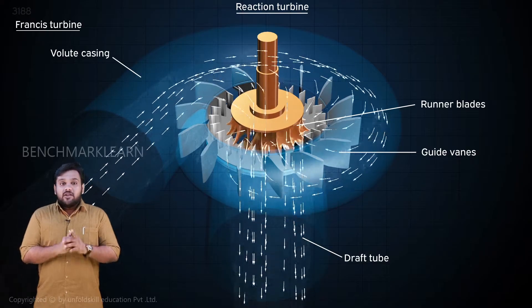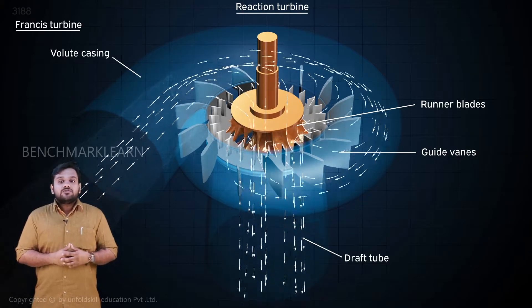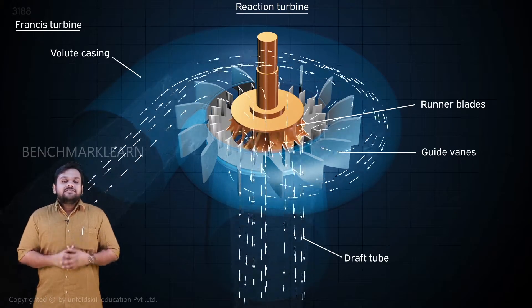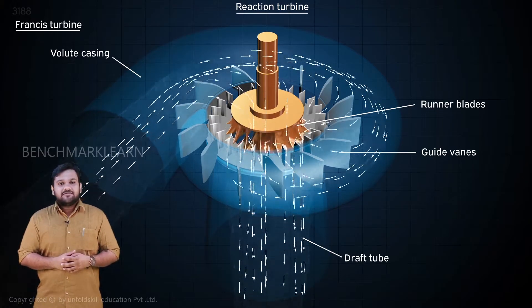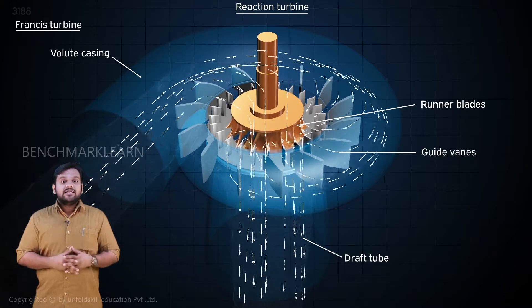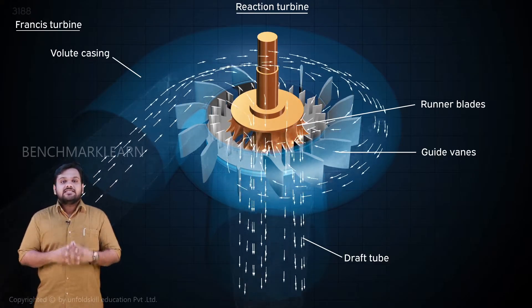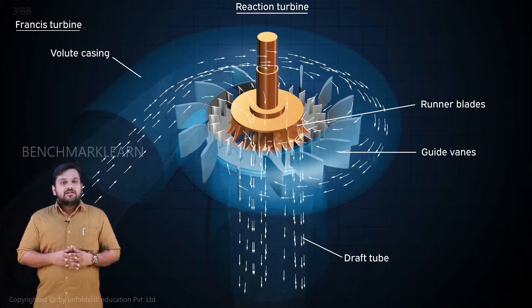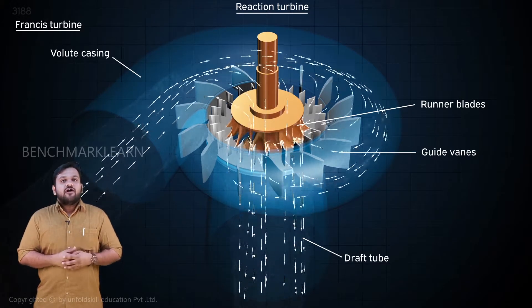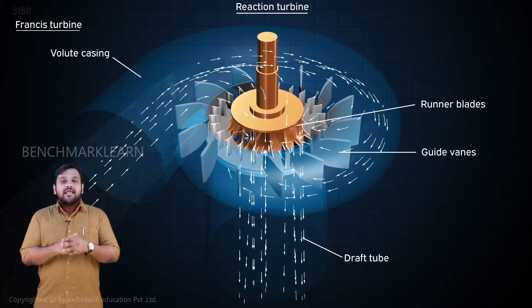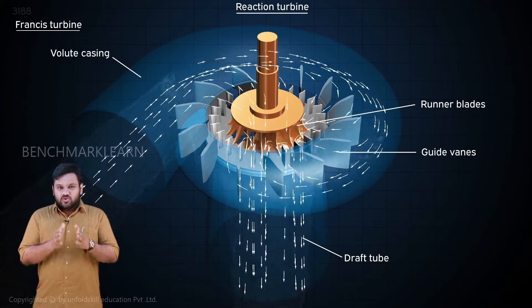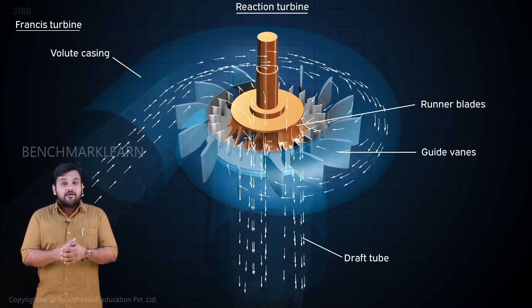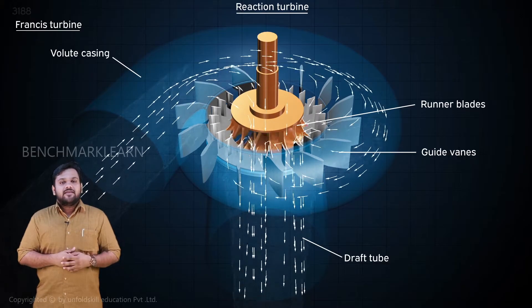Water at low pressure from the turbine flows through a tube called a draft tube. This has a gradually increasing cross section, so the pressure increases and the velocity decreases during the flow in the draft tube. At the end of the draft tube, the pressure of water will be at nearly atmospheric pressure. This eliminates the possibility of water going up from the reservoir to the turbine.